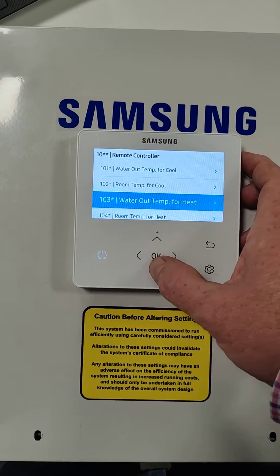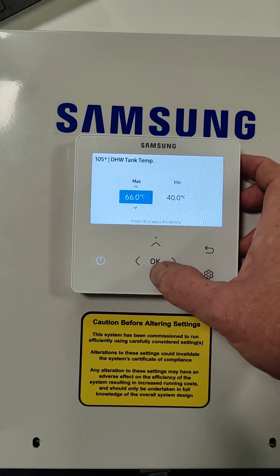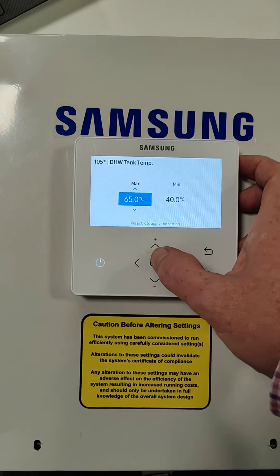And you need to set this up to 65 degrees C, press OK. Then you have to go to 105, domestic hot water tank temperature, and again set this up to 65 — that will be enough.